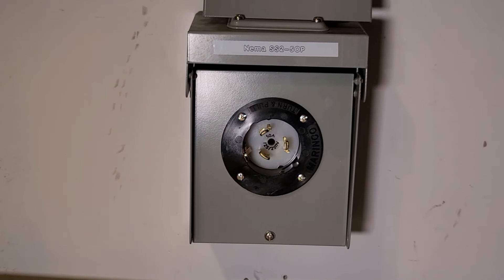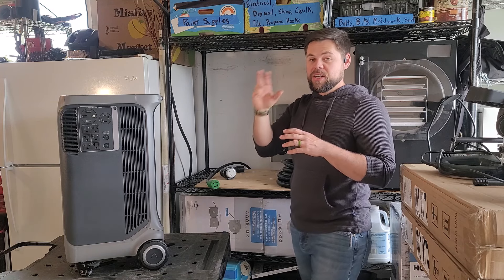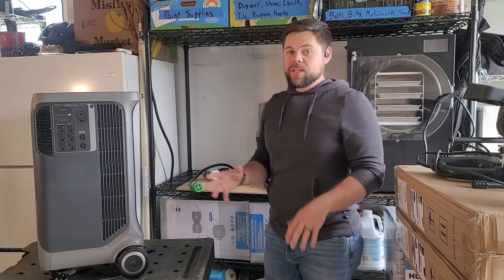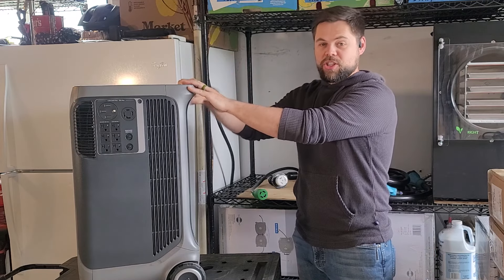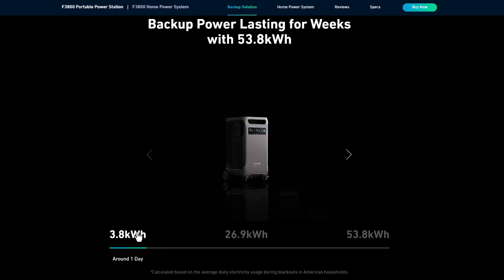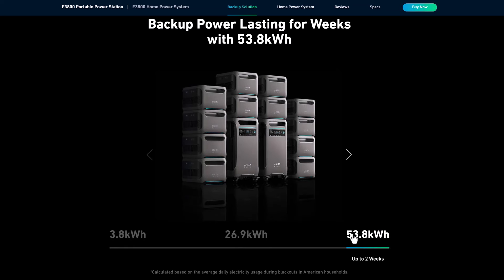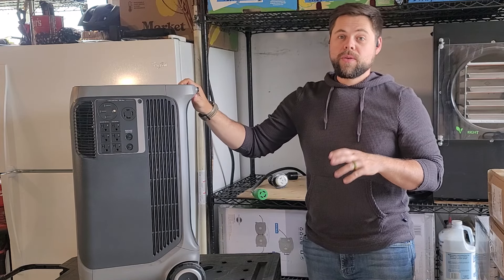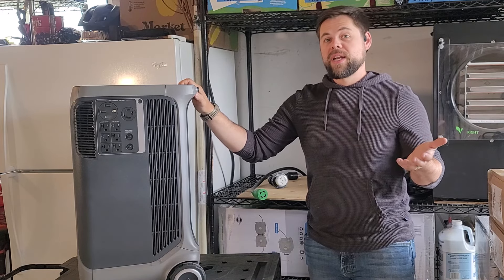I have an SS2-50P generator inlet that connects directly to my electrical panel, where I have an interlock switch. It's very similar to a transfer switch but it's meant to run the entire electrical panel rather than just a sub-panel for critical loads. I always recommend the SS2-50P inlet because it's rated to 12,000 watts — if you get two F3800s you can link them together for 12,000 watts of output, which you'll need for electric water heaters, electric dryers, large air conditioning, or electric heat. I mostly run on propane, so 6,000 watts is more than enough.